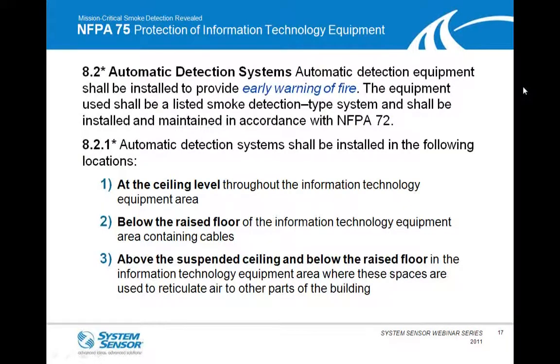So if we go into NFPA 75 a little deeper, as I alluded on the previous slide, it does call out for automatic detection equipment shall be installed to provide early warning of fire. The equipment shall be listed smoke detection type, and shall be installed and maintained in accordance with NFPA 72. So it does ratchet back up to NFPA 72. With the automatic detection, it does call out that 3 different areas where detection should be used.